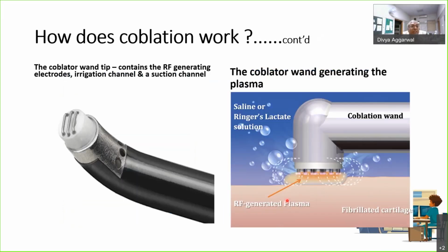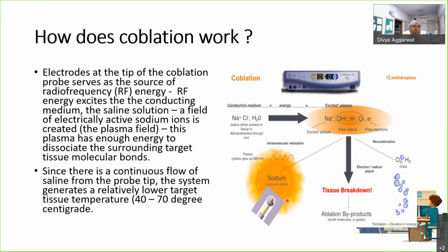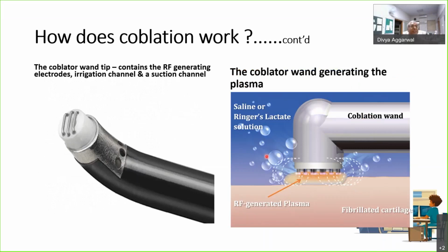Coming back to the slide where I was, I said that a coblator will work only if there is saline. So since there is a continuous flow of saline, the temperature that will be generated will be very low. It will be of the order of 40 to 70 degrees. Whereas, as I said, it is almost 700 degrees centigrade for a traditional electrocautery machine. So the collateral tissue damage, you can understand, will be much less. So this I have explained already.